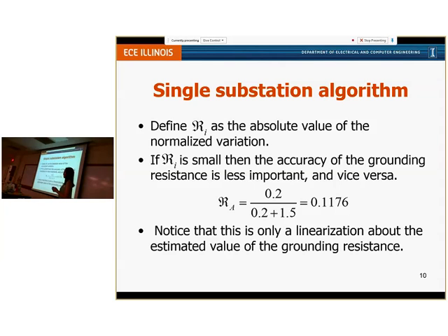Now we define scripted R_i as the absolute value of the normalized variation. If the value of R is small, that means the accuracy of the grounding resistance at that substation is less important, and vice versa. In our case study, the scripted R of substation A is equal to 0.117, which means that if the grounding resistance of substation A varies by 1%, then the GIC at substation A will vary 0.1176%. However, if that grounding resistance increases 100%, then using simulation we got that the GIC of that substation only decreased by 10.6%, because this is only the linearization about the assumed grounding resistance.